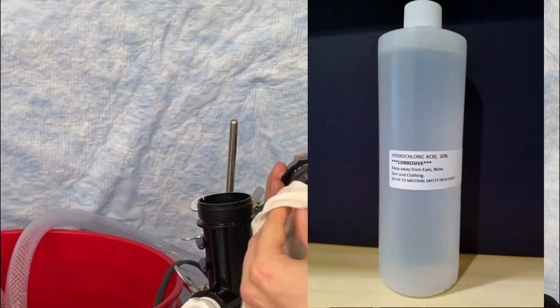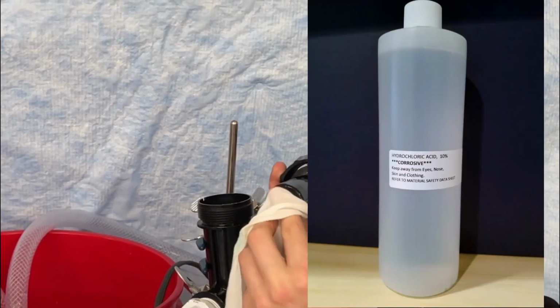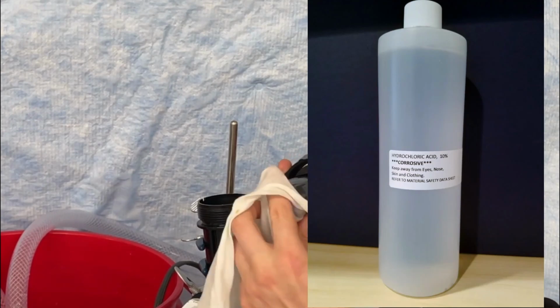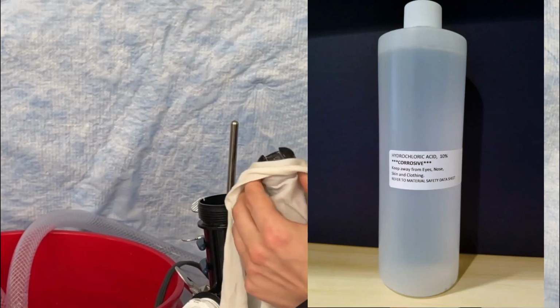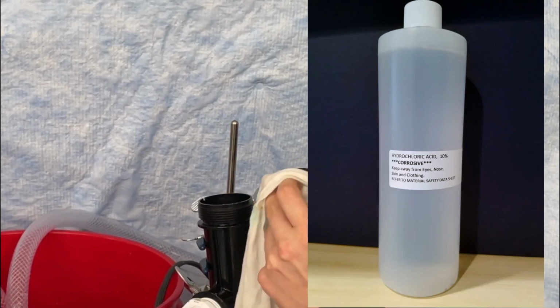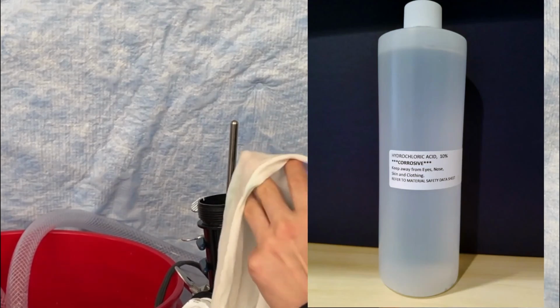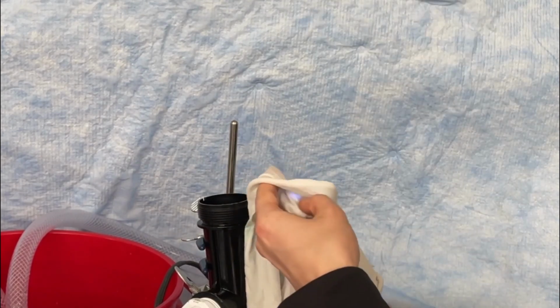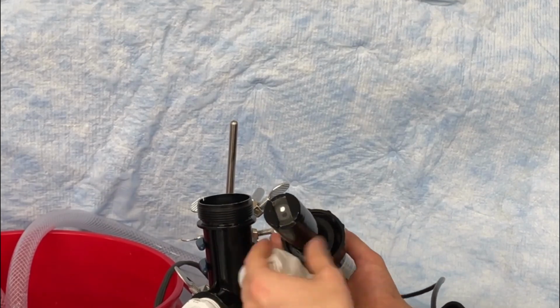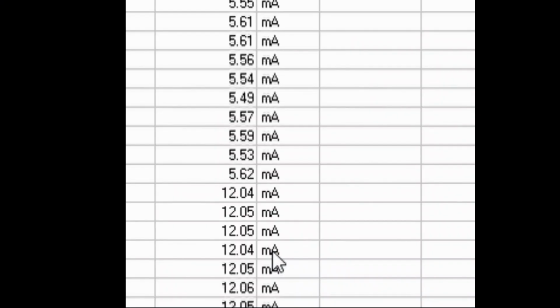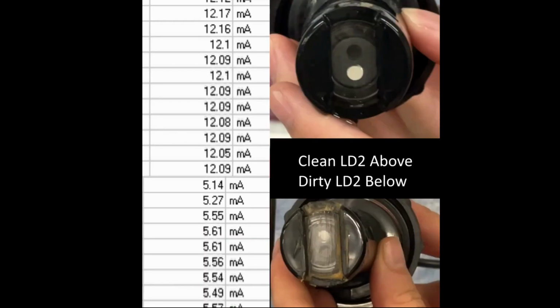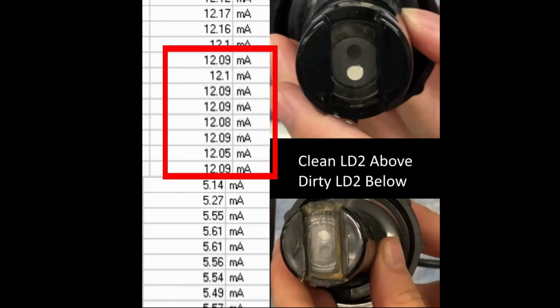probe. Hydrochloric acid should be used sparingly and only as a last resort. 10% is the concentration that we recommend, and we also suggest handling the solution with gloves. Now is the time to check and see if the readings have returned to normal. We can see now after cleaning, the values that were originally 5 milliamps have now returned to 12 milliamps, very similarly to our first clean LD2 that we had, that was reading around 12 milliamps as well.